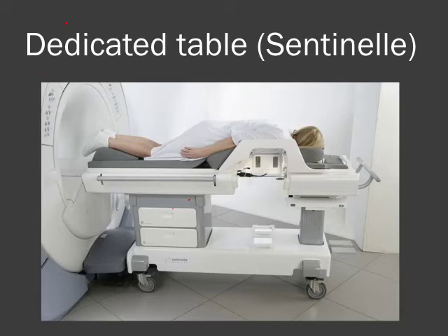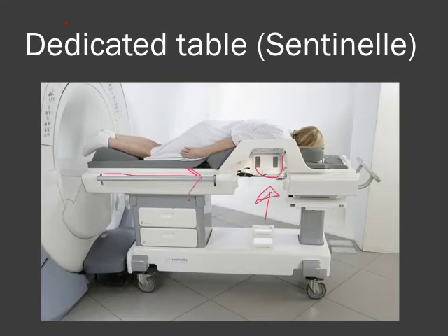There are a number of different dedicated breast imaging tables available on the market. This one is marketed by Sentinelle. The breasts come through and have coils positioned here, and there is a lot of space underneath. The patient is at the same level as the regular table, so much bigger patients can be accommodated, and there is really no practical limitation on breast size using a dedicated table. This table is simply wheeled in and out, and when patients have a biopsy, they can be wheeled straight out into another room for recovery.